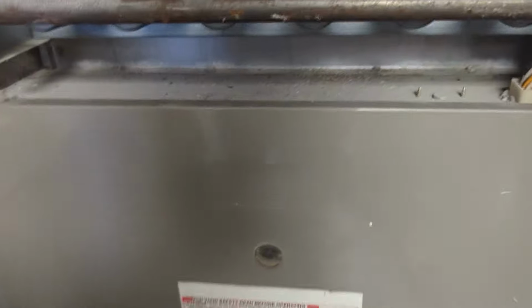You can hear it's working, but you can't see it. The blower started up right away, so we're like, yes. Unfortunately, though, it's in really, really poor shape. I think we're going to order a motor just to be proactive about it, because we think that thing's days are numbered, especially with a new capacitor in there now. It's going full on, and now it's probably going to die. So anyway, they're like, oh, thank you so much.